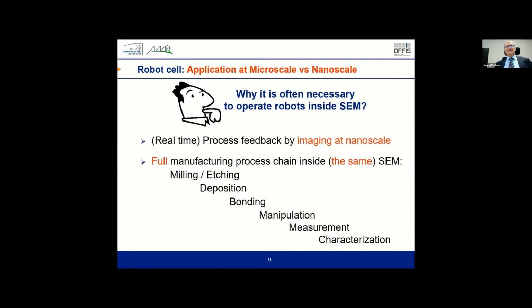The second reason is you can have a full manufacturing process chain inside the same device, inside the same vacuum chamber of a scanning electron microscope. From the very beginning, you fabricate nanostructures using milling or etching by FIB or electron beam, then electron beam induced deposition, nanobonding, manipulation by robots, measurement, characterization, quality check, etc. You have the whole chain in the same vacuum chamber, enabling rapid prototyping in a very easy way. This is a very special merit of this technology.